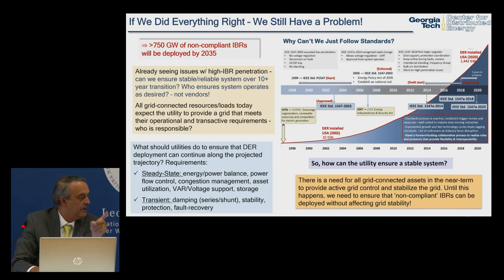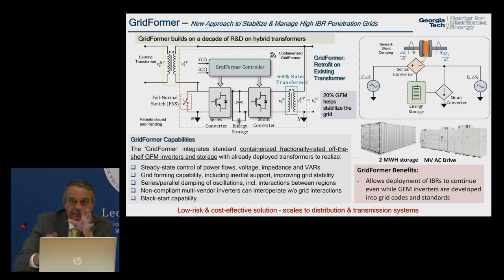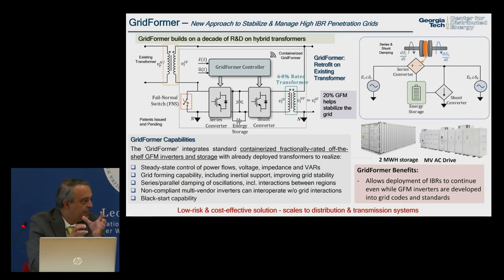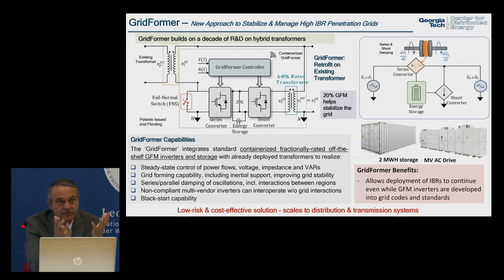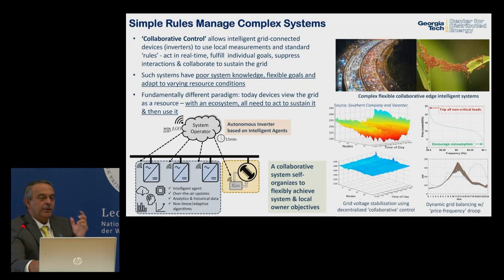We've proposed attaching existing medium-voltage converters and drives to existing transformers to create what we call a grid former — providing grid-forming capability on the grid with series and shunt damping to stabilize the system. This is an example of a lower-risk, cost-effective solution that can scale to both distribution and transmission levels.